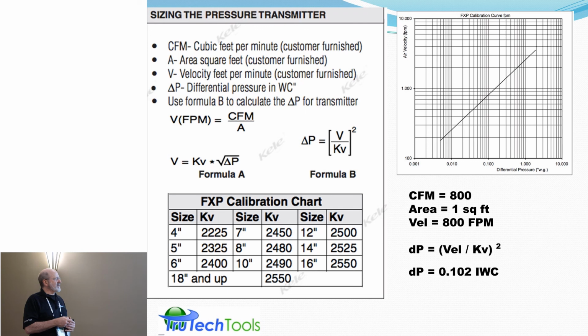I did a quick calculation here. If you had like 800 CFM over a 1 square foot area, you'd be in the 1/10 of an inch of water column range, which is sort of like the sweet spot of operating for a lot of pressure sensors. But if you get down to lower velocities, you're going to get to much lower pressures, and it's going to be hard to extract information from these.